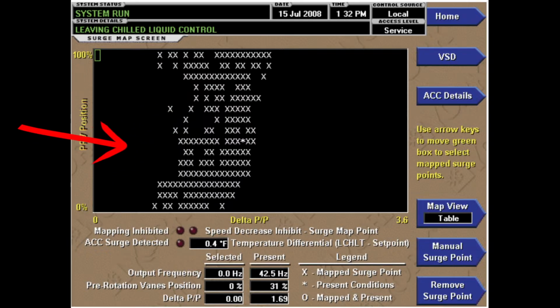And I'd have to find the pictures of it, but I've had these where literally this whole left side of the map, which is where most of the points are going to graph, is nothing but a big white X. Okay, that's not okay. That's not normal. And what that will cause, especially with a variable speed, we have output frequency, right? So this is a variable speed system. It's going to cause this to max out at 100 at full 60 hertz all the time, or 50 hertz if you're overseas. So you're going to be sitting up here in the maximum speed all the time.